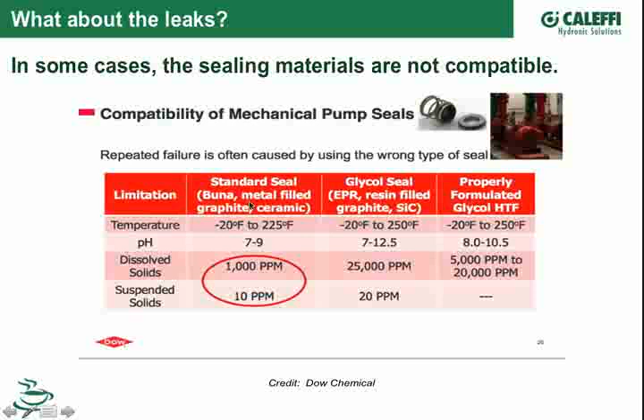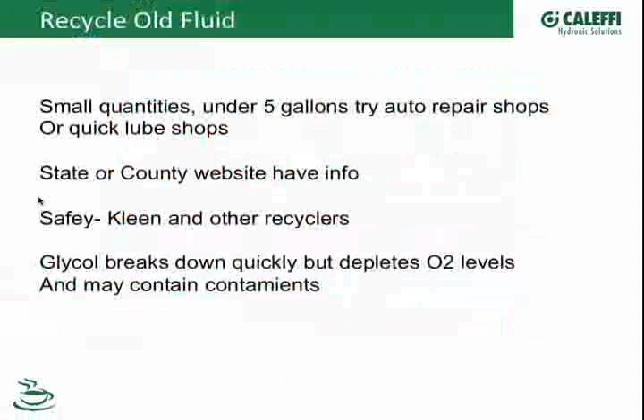I would say most of the pump manufacturers in our industry for hydronics now have seals compatible with glycol. Most equipment we use will say glycol compatible, and they typically give you a percentage. I don't know that you'd have to ask the pump manufacturer for a special type of seal. Is that your experience too, Kevin? Most pump manufacturers will have a recommended seal for glycol, yes.